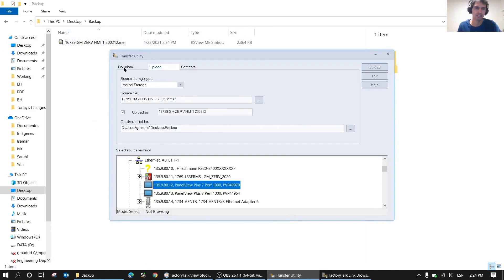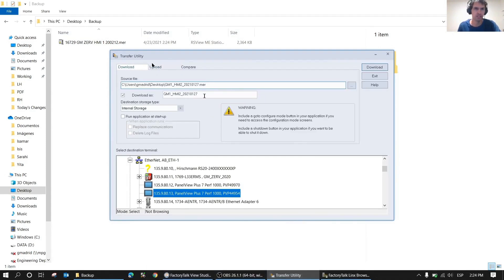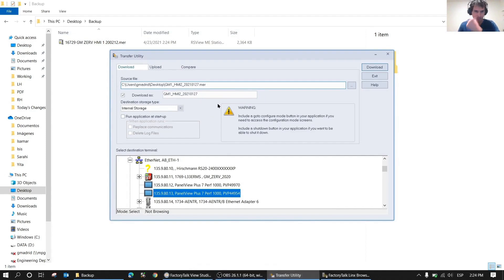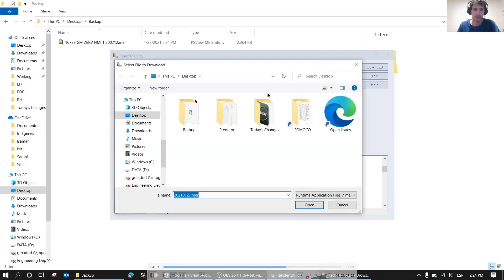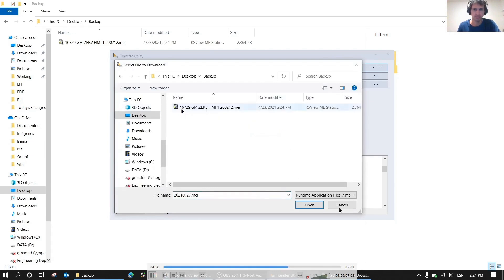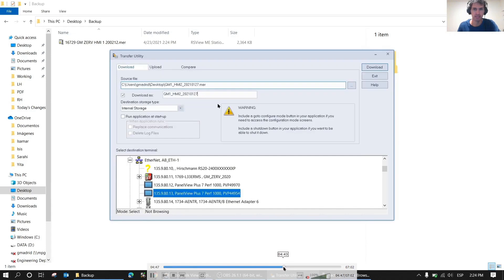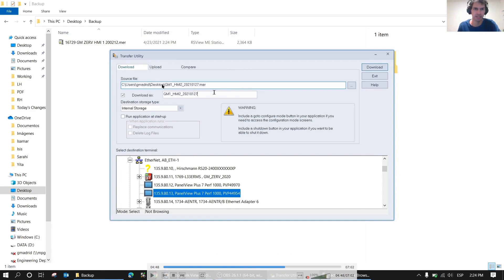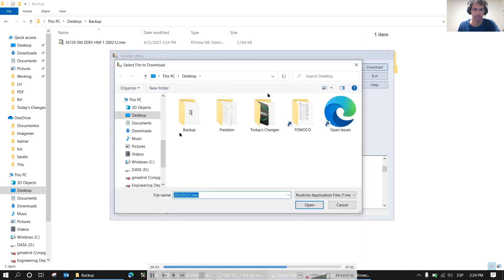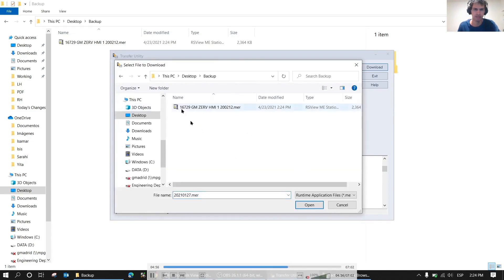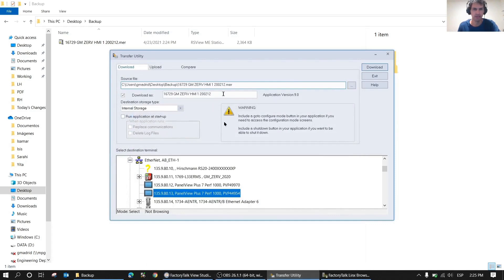Here precisely is our backup, which is a runtime.mer for PanelView. What we're going to do now is download the same one without making modifications. When downloading, we can also change the date. We select download and set today's date. First we're going to choose the runtime. It's pointing to one on the desktop, but the one we're going to download is in the backup folder we generated. We click on the three dots, look for our backup in the backup folder, and click open. Here we're going to change the name with the current date.